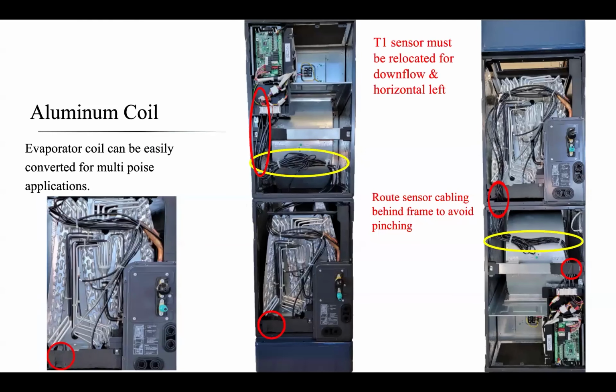All right, so here's the downflow. Let's talk about the downflow application. When you flip this in downflow, you're going to pull apart your plugs for the wiring. You only have to pull apart the plugs for the sensors, the EEV, and the A2L sensor. You do not have to pull the motor plug. So you unplug your sensors and release your wiring from the wire ties, which are releasable and reusable. Drop your wiring on top of the coil, unbuckle it, take the blower module off the top, flip it over on its head, and then pick up the coil and set it right back on top of the module of the blower.